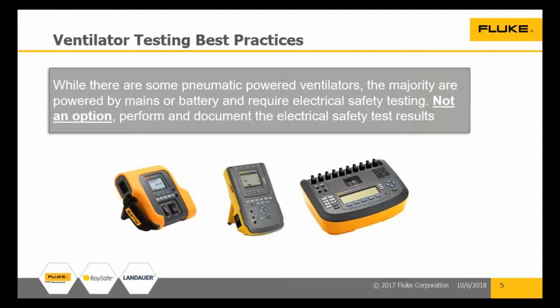What do you call the electronic component that is a conductor, insulator, conductor? Capacitor. And that is exactly what we're going to use in order to get this measurement. So you take a 10-inch square of aluminum foil, and if it's very thin aluminum foil, double or triple it up, make your 10-inch square, tape it down to the touchable surface of the device. Now, having done that, we have conductors inside the medical device, yes? The outside covering is plastic, that's conductor or insulator? Insulator. And then we have our aluminum foil, which is a conductor. We have formed a capacitor, and that's exactly what happens in real life.